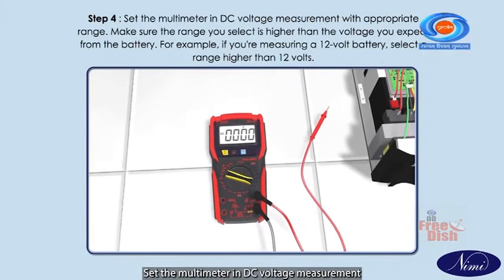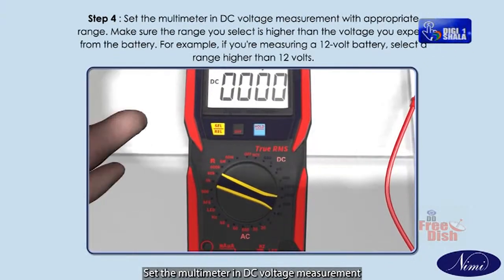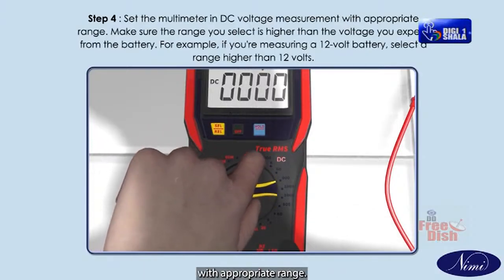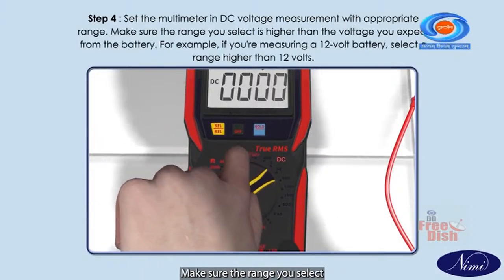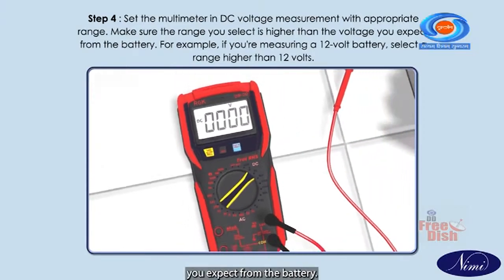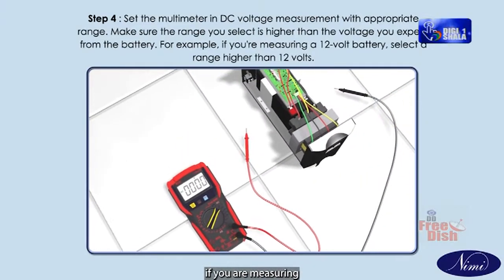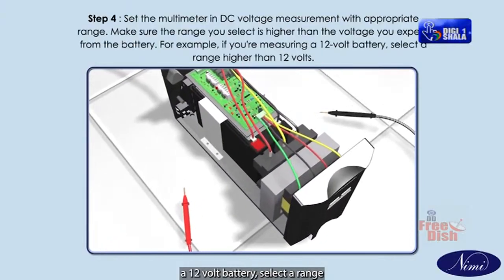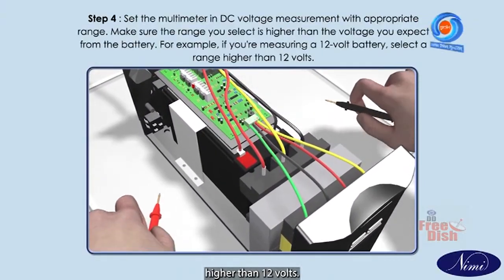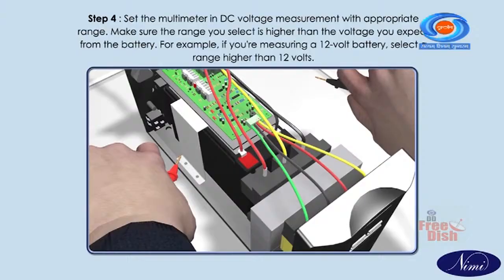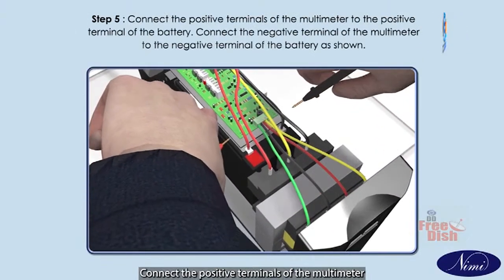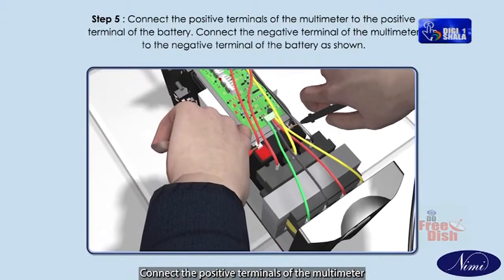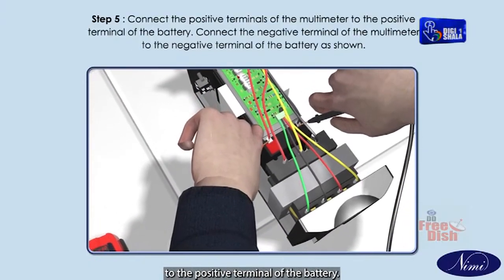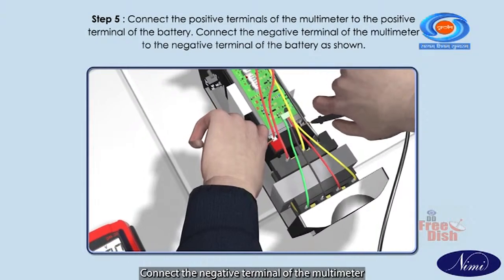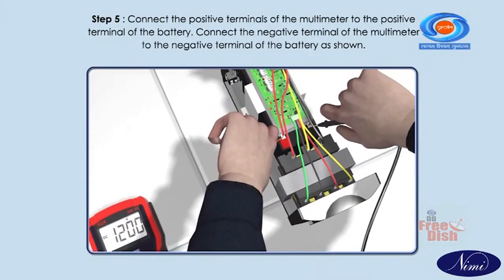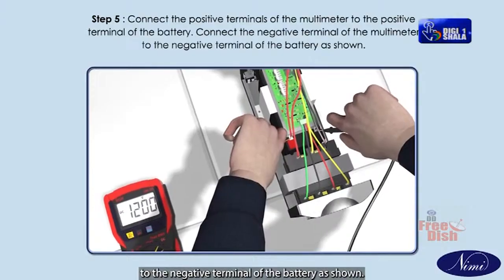Step 4. Set the multimeter in DC voltage measurement with appropriate range. Make sure the range you select is higher than the voltage you expect from the battery. For example, if you are measuring a 12 volt battery, select a range higher than 12 volts. Step 5. Connect the positive terminal of the multimeter to the positive terminal of the battery. Connect the negative terminal of the multimeter to the negative terminal of the battery as shown.